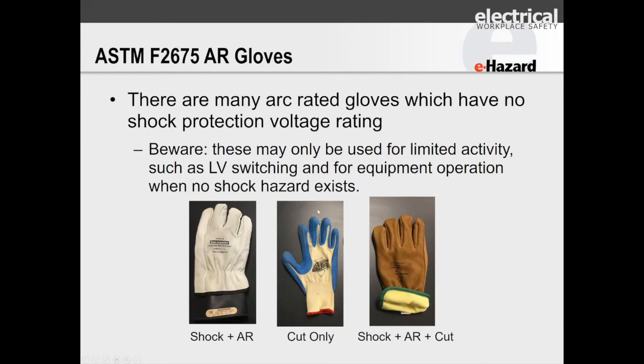Cut-resistant gloves may look pretty good. This one does have Kevlar in the back, so that's very protective from flame, but the actual coating is not flame resistant on this one, and I've actually ignited that glove. And not that it's a bad glove, it's made for cut. Use it for cut. Don't try to use it for arc flash just because the back says it's Kevlar. There are arc-rated gloves that look just about like this, but they actually are flame resistant and will have a protective value, and they'll be rated and usually labeled with a protective value.